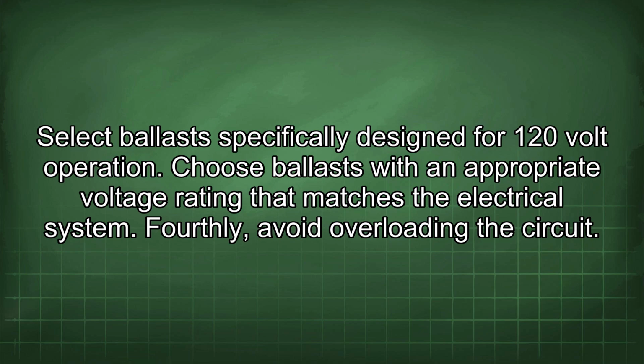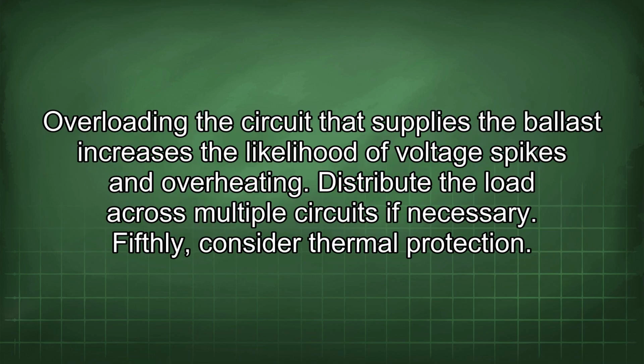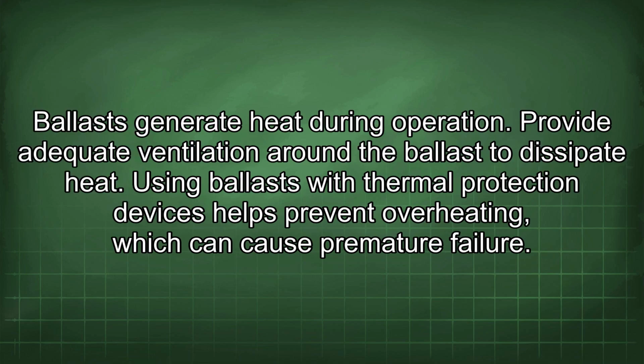Fourthly, avoid overloading the circuit. Overloading the circuit that supplies the ballast increases the likelihood of voltage spikes and overheating. Distribute the load across multiple circuits if necessary. Fifthly, consider thermal protection. Ballasts generate heat during operation. Provide adequate ventilation around the ballast to dissipate heat. Using ballasts with thermal protection devices helps prevent overheating, which can cause premature failure.